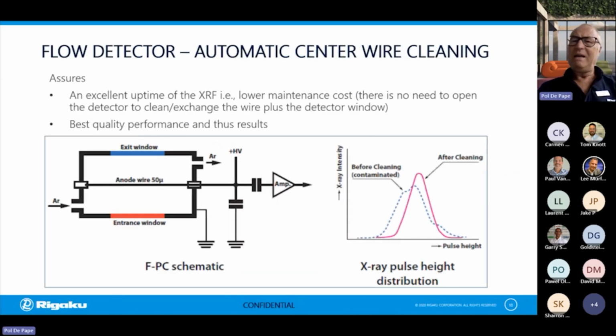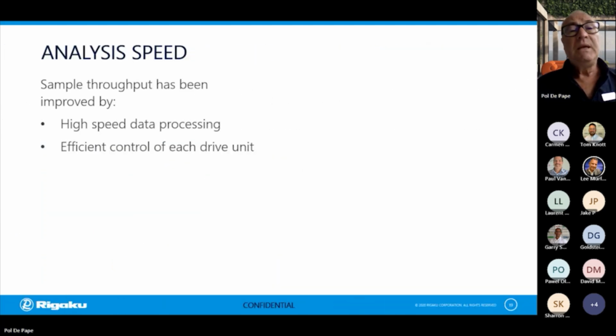This automatic center wire cleaning, I want to highlight a little bit, because if you need, let's say, to do your pulse height analysis and you can see that, well, the energy distribution is not that nice anymore, it can be because this anode wire, which is in the middle of the detector, is dirty. And if it's dirty, it needs to be replaced, or as Rigaku does, we put the high voltage through this wire and we clean it automatically. So we do not have to open the spectrometer. We do not have to build out the spectrometer, open the windows and exchange the anode wire. We don't need to do all this. So it's a matter of 5 minutes and we can clean the anode wire. So instead of losing 1 or maybe more days just exchanging this wire, we can do this in 5 minutes, meaning uptime, of course.